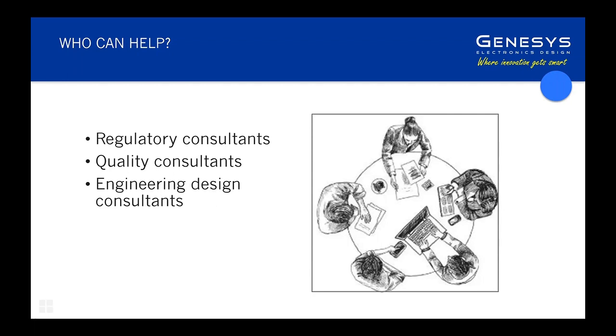On the level of the applicable standards, I noticed from the list, I know you're not listing all the applicable standards, but on the safety side, there is another important standard to be considered sometimes for certain devices, the 61010, along with 60601, which is applicable to a good number of devices where they are used in the labs. So that's one. And one standard that blends well with risk management, which used to be part of the risk assessment, is 62366. So that's probably worth mentioning if this presentation comes up again.